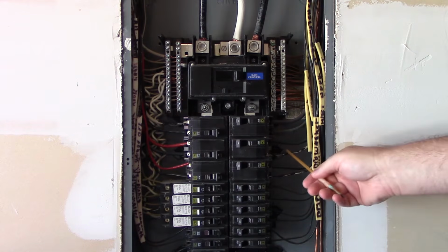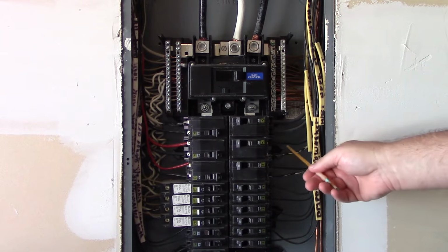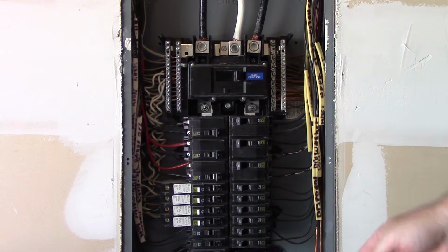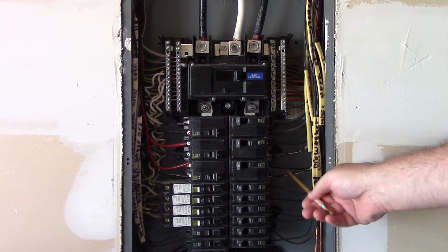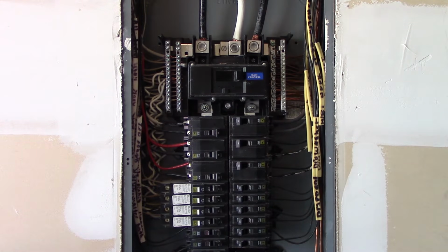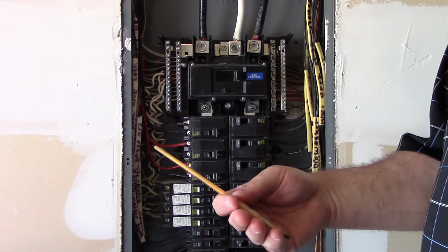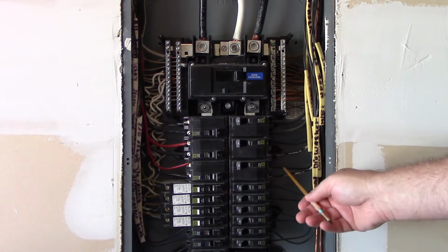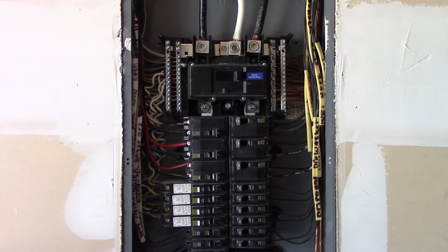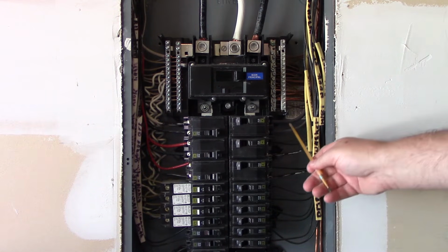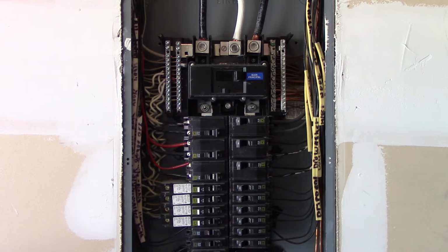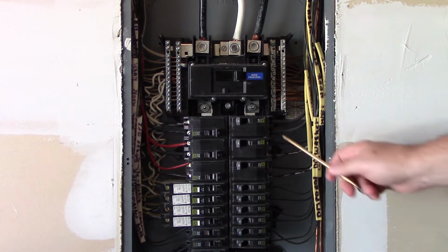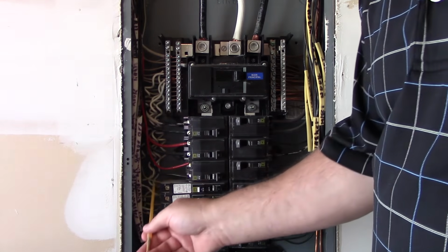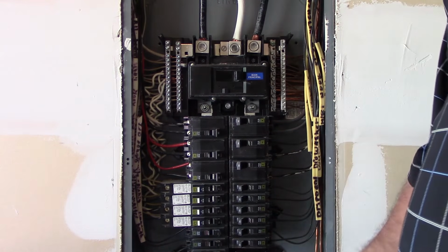There's a couple of those in here that they do that on. Here they happen to use the Sharpie. Again, as a home inspector, I'm not worried too much. They made the effort to mark these, so I'm going to go with that. As a municipal inspector, if you're doing an inspection on a rough-in or the final, you make sure that they put some tape around it. All right, so everything looks good down here. I don't see any issues with that. I do the same on this side, and I look at all these terminals to make sure that they're all in good order. The next thing I want to do is use my IR.